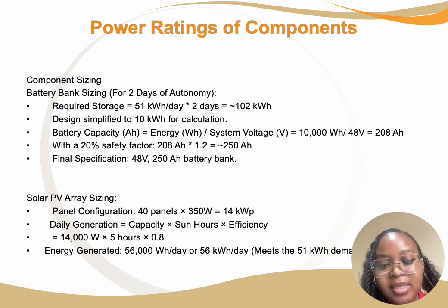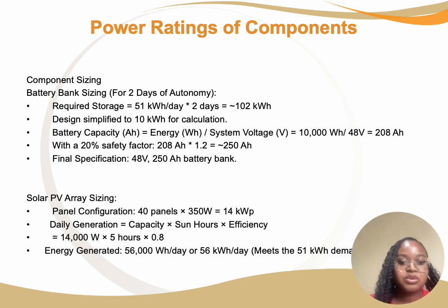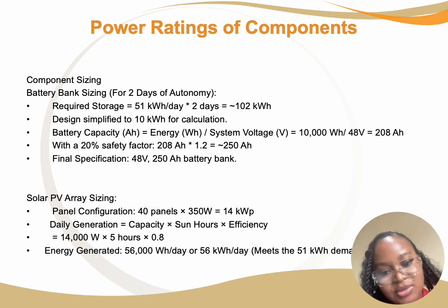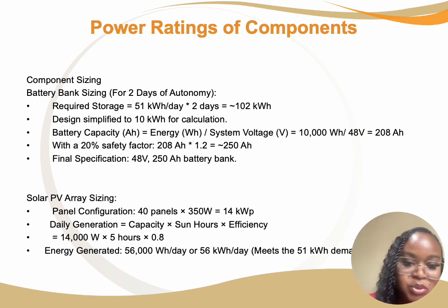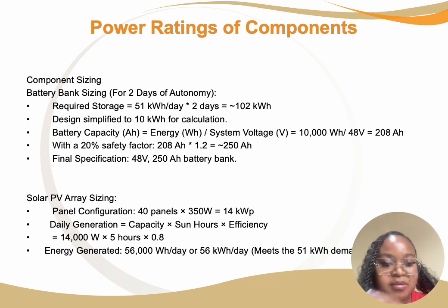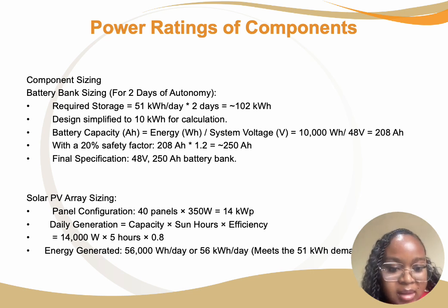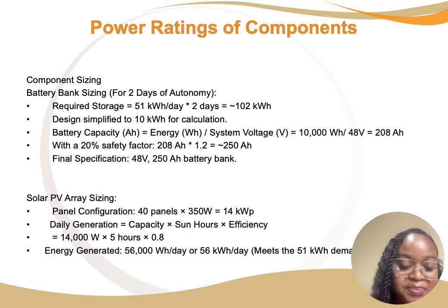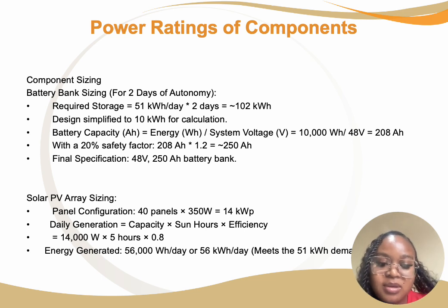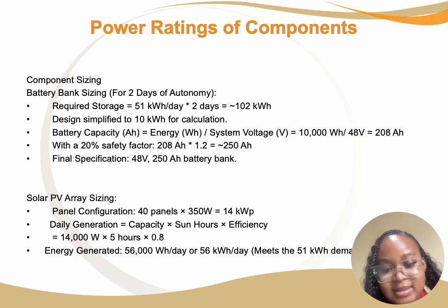10,000 watt hours divided by 48 gives us 208. For our safety factor, we multiply that by 1.2 and then we get 250. So our final specification is a 48 volt, 250 amp-hour battery bank. And then we calculated our solar PV array sizing. Our panel configuration is 40 panels times 350 watts, which is 14 kilowatts peak.